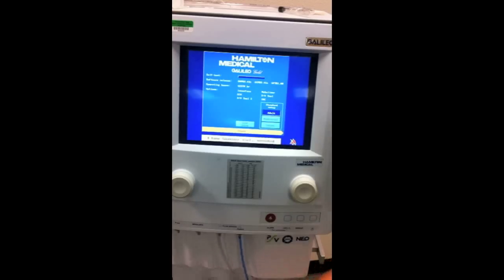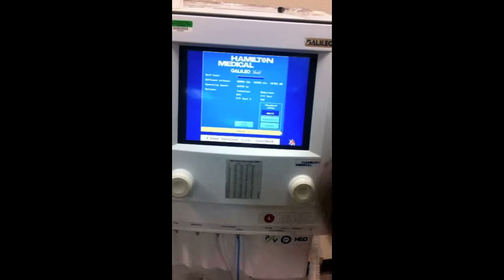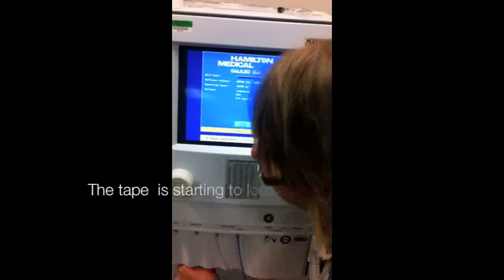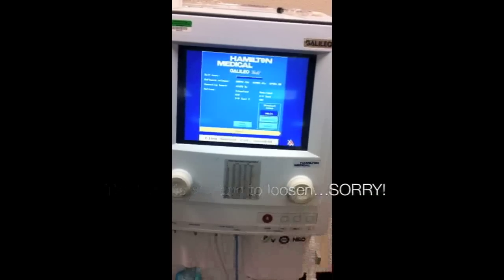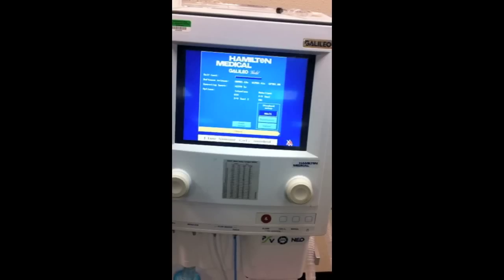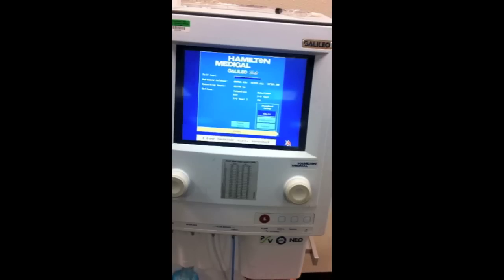Humidifier. We have our filter on the inspiratory side. See here, we got an arrow pointing out. Remember I told you every ventilator helps you out by knowing which one's inspiratory and which one's expiratory. So pointing out goes to our patient. We hook that there with our filter to one side of our humidifier. Inspiratory is always going to go to the humidifier, and then the inspiratory line going to our patient, and then expiratory into our exhalation valve. This one has an external exhalation valve.